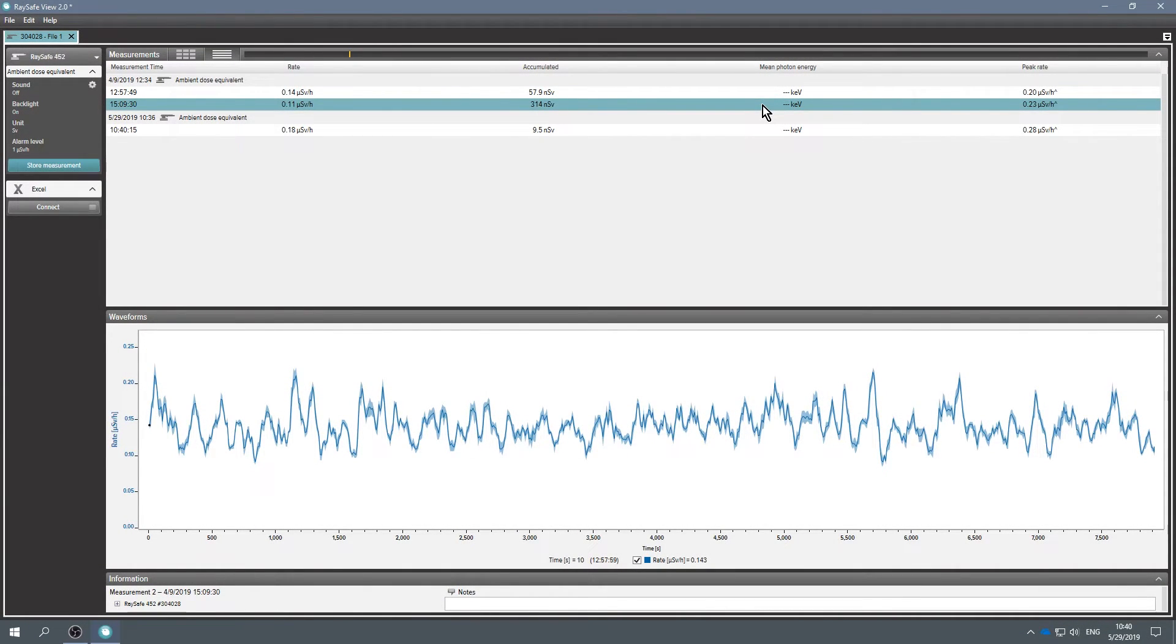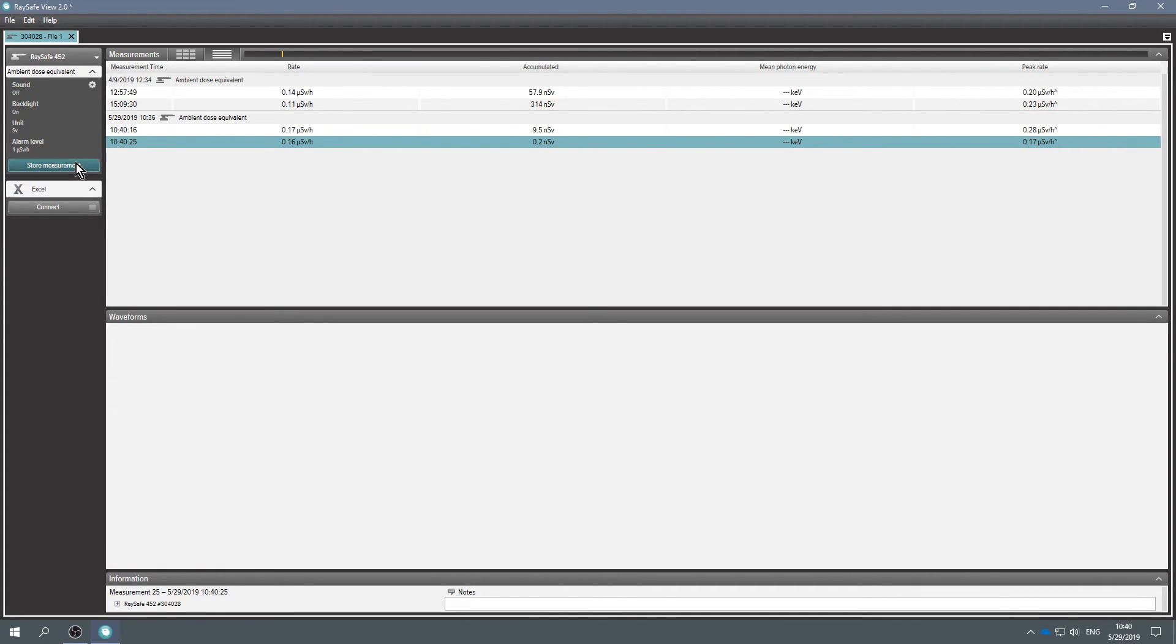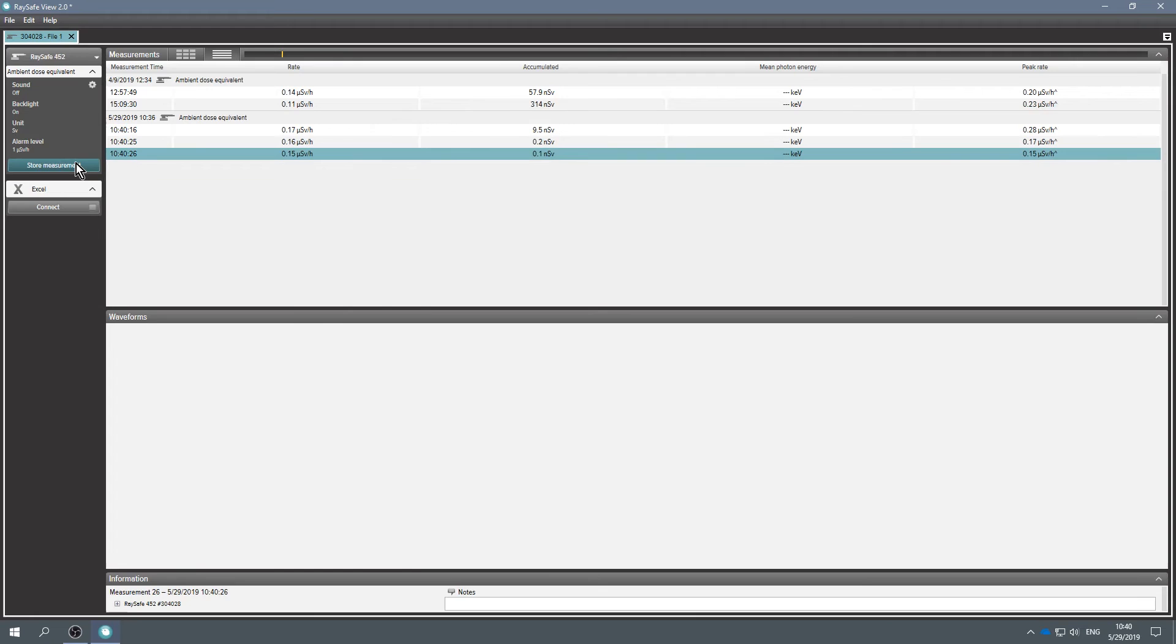After 24 hours of measurements, a new measurement begins automatically as a new row in RaySafe View. You can also store a measurement directly in RaySafe View at any time by clicking Store Measurement.